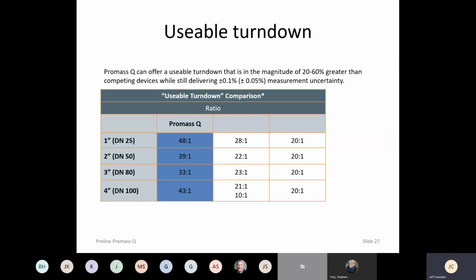So the Promass Q meter has a 48-to-1 usable turndown. So from a 14.5 pound drop to where you'll no longer achieve 0.1% accuracy is 48-to-1 on a 1-inch meter, a little bit less on a 2 and a 3, 43-to-1 on a 4-inch meter. Okay, and those other numbers there are some of our competitors. So you can see that the Promass Q just leaps and bounds ahead of some of the other competition out there as far as usable turndown.